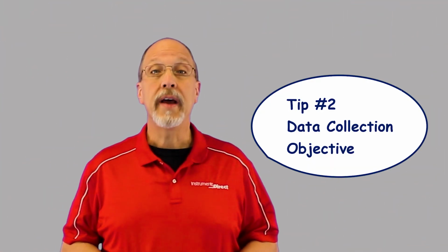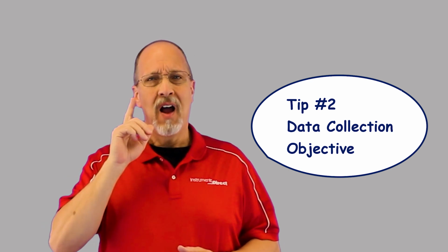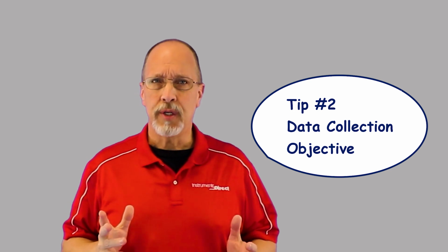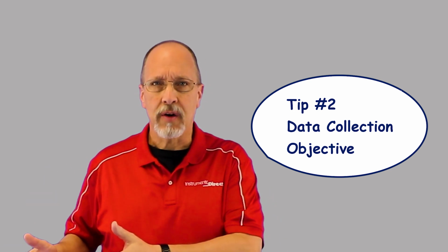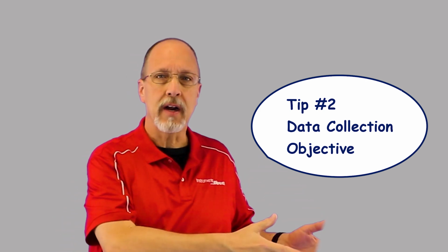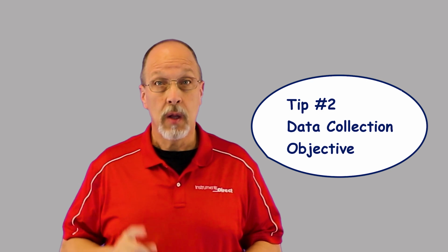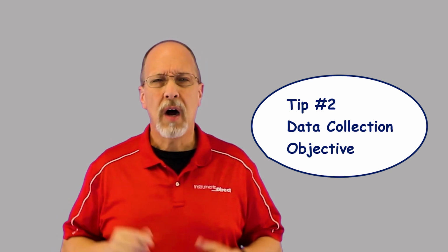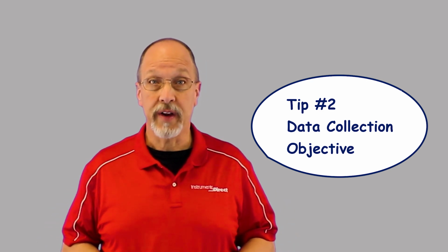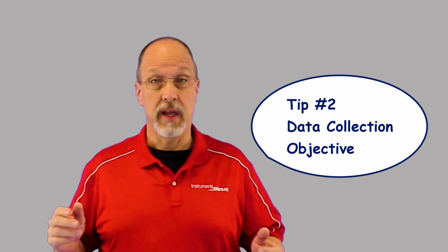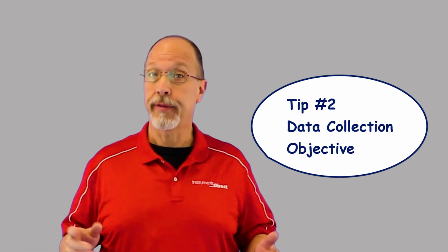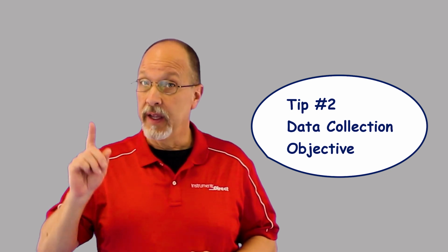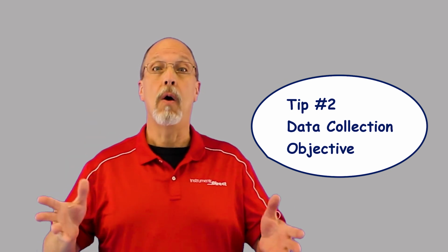Which brings us to tip number 2. What is your data collection objective? Are you just spot checking? Doing a quick test here, monitoring flow rate, and then picking up and moving over here and testing again, and then writing everything down in your test report? Or are you hunkering down for an extended flow survey for an hour, a day, a week, a month, perhaps even longer? If so, you'll have to data log all that information.